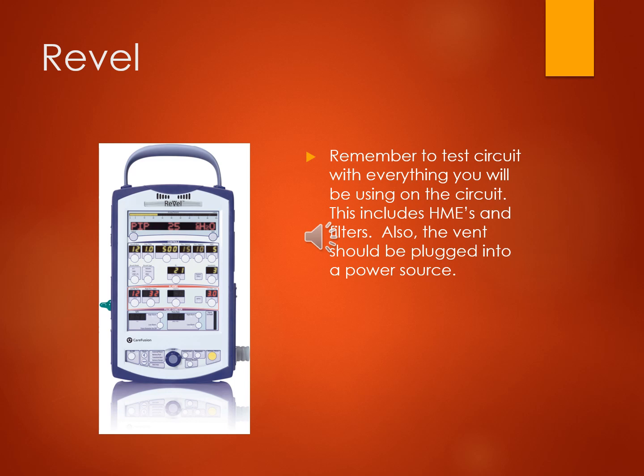All right, well, I already mentioned making sure all those things are in line when you're testing the system, but also you should make sure the ventilator is plugged into a power source when you're doing that. You're just going to get the best results that way. And then also, if you're going to be transferring back and forth, don't trust that internal battery. We don't know how long ago that had been swapped out.